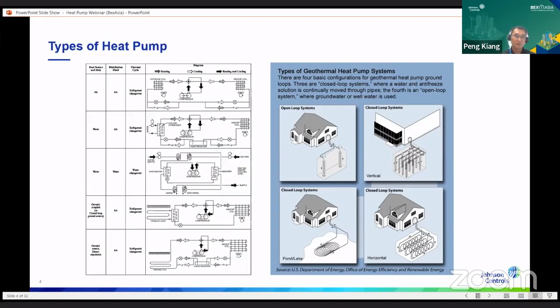Your chiller's control point is the chilled water temperature output. Whereas a heat pump operates at a much higher pressure level to create more hot water on the condenser side, and as a result, the control point is the hot water output of that heat pump.